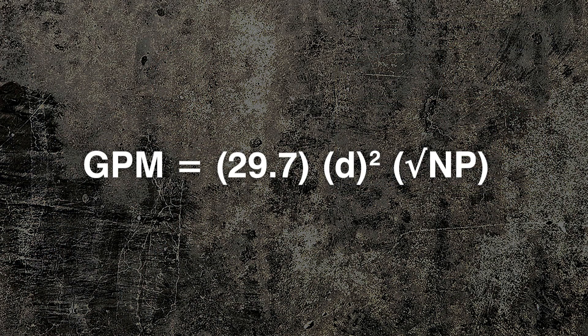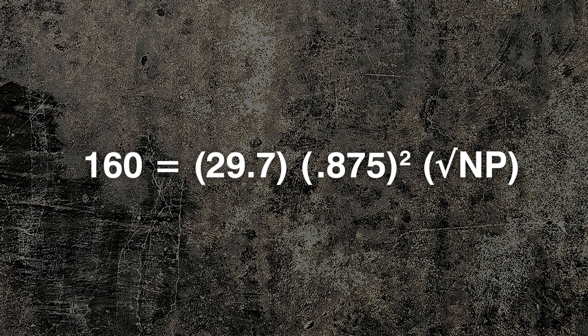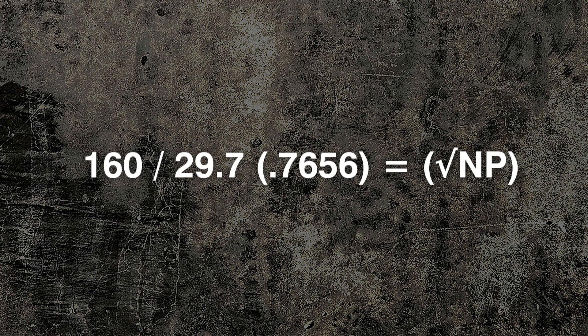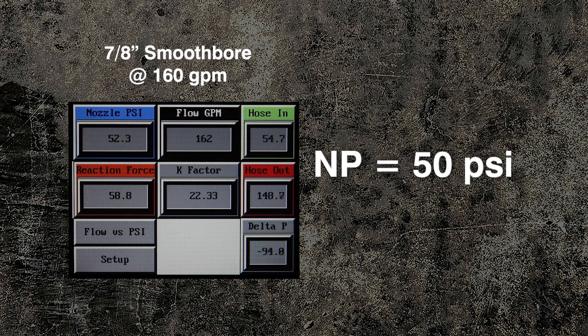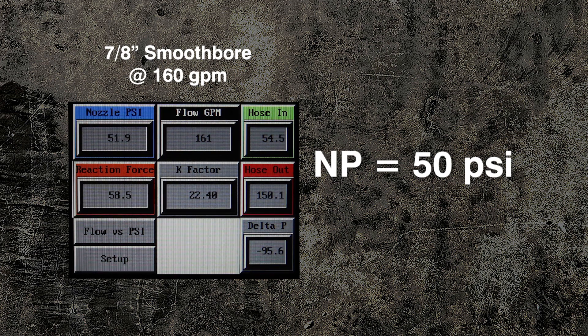Comparing the formula to our flow test results, we see that flowing at 160 GPM with a 7/8-inch smoothbore, we should be getting about 50 PSI nozzle pressure. As you can see, reality matches the formula.